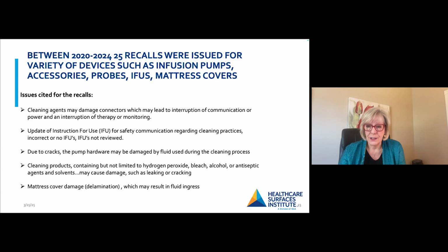And when damage occurs, I just want to add this here as well. When damage occurs, you're creating tiny microbial reservoirs where microbes can actually get into those areas and colonize up to a point where it becomes very difficult, if not impossible, to actually continue cleaning that device. And at this time, there's no research to let us know when this device should be removed because it is a patient safety risk.